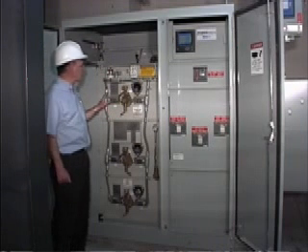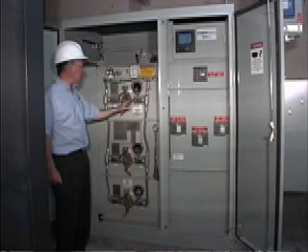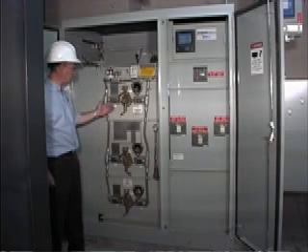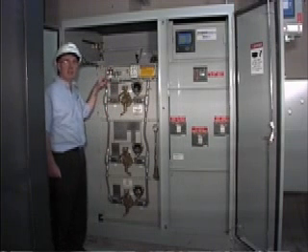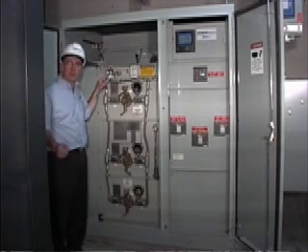This customer has also ordered the SCADA package, which includes the switch position indicators, which are contacts, so as the switch is rotated it will indicate the position of the switch. That's on all three switches. It also includes the gas pressure gauge. Each unit comes complete with a standard gauge to tell you what the pressure is at various temperatures, because the gas pressure will fluctuate with temperature.